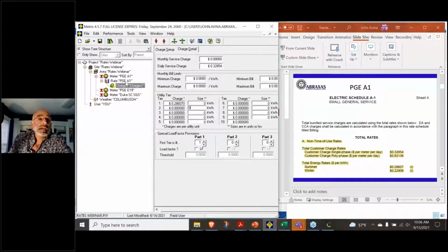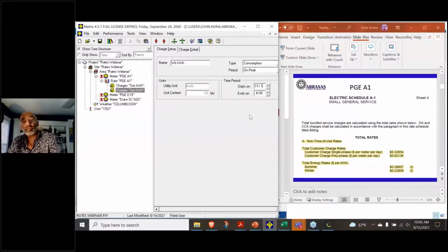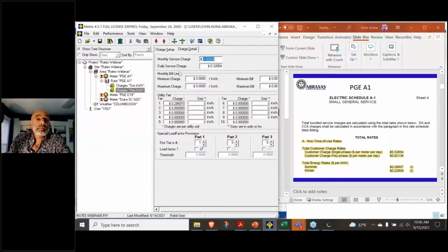All right, and then I'm going to also add a winter charge. So I'll drag this up and I'll just make some changes to it, and I'll call this winter. And this will be 11/1 to 4/30. A lot of times in class, people have asked, does it wrap? It does wrap, so I don't have to put it in twice, 11/1 to 12/31 and 1/1 to 4/30. I just put in this and it knows what to do. I will put in the daily charge is the same, but the dollars per kilowatt hour charge changes, and it is 0.2290. Okay, that's it.